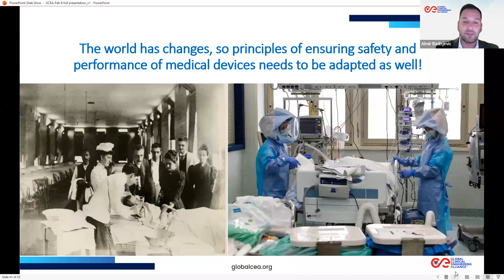A medical device is, let's say, like some kind of person. It must have personalized preventive maintenance and management. Only based on real measurements from that device, taking into account all of the parameters, from the working hours to the history of the preventive maintenance, can we talk about very planned and very accurate maintenance and management of medical devices. So that's something very important now. Next slide, please.